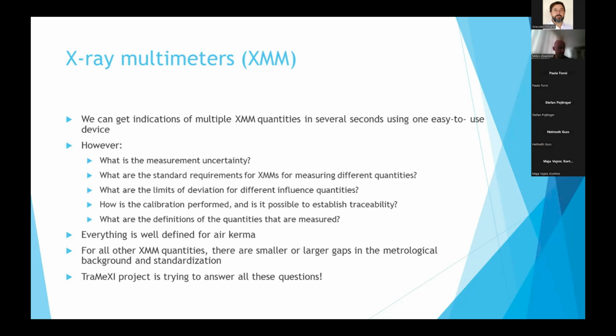And you will find that for several quantities, there are actually no standard requirements and no IEC standards or other standards. And then you will probably also wonder how other influence quantities influence your measurements. For example, how does the ambient temperature influence HVL measurements or time measurements or whatever? And again, because there are no IEC standards with requirements for measuring devices, you will probably not be able to find how different influences influence your measurement.